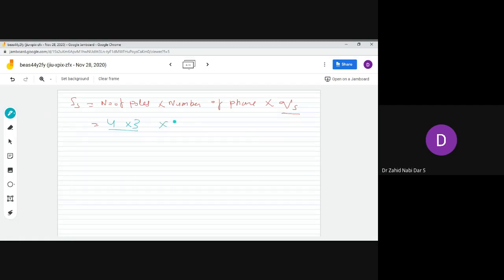So the first value you will get for stator slots is 36. The second value will be 12 into 4, that is 48. The third value would be 60. The fourth value would be 12 into 6, 72. So this is first, second, third, fourth. Instead of into 3, we will do into 4, into 5, into 6. So this would be common.